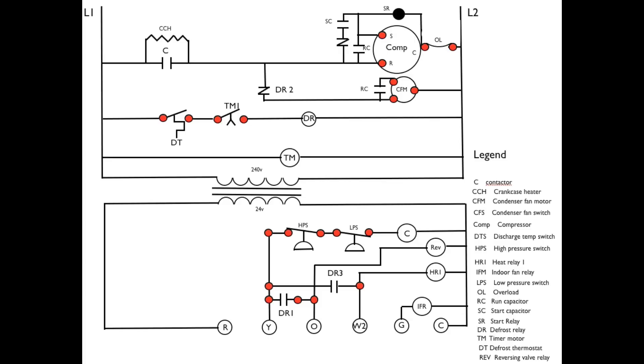This one's a little bit different — this is actually a heat pump. It has a reversing valve in the low voltage that changes it from heat to cool. It also has an O terminal that energizes the reversing valve in cooling.